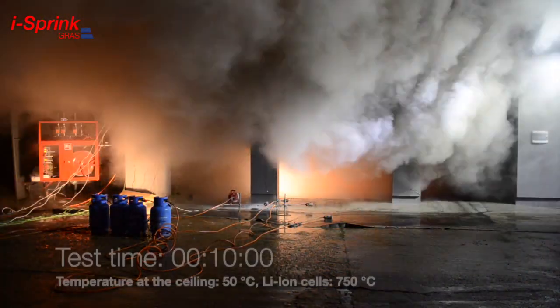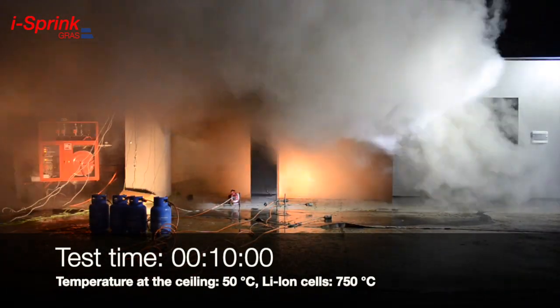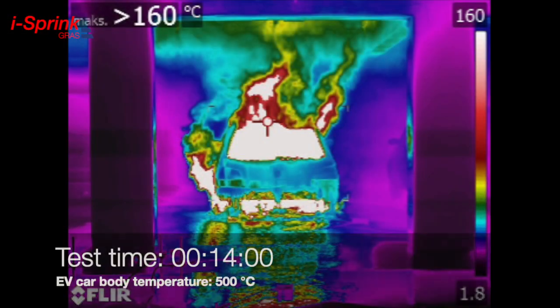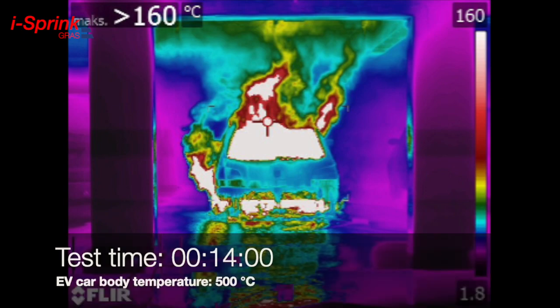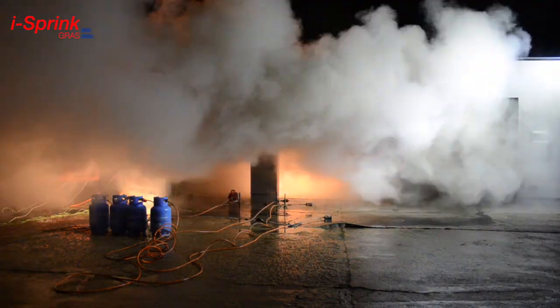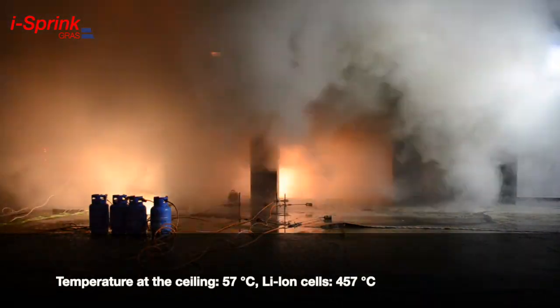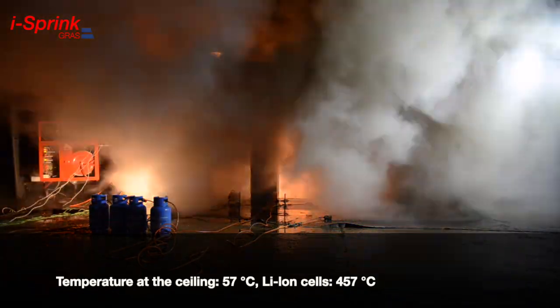At 10 minutes of fire, the temperature at the ceiling above the burning vehicle is only 50 degrees, while on the lithium-ion cells it is 750 degrees. The thermal imaging camera indicates that the temperature of the body of the electric vehicle reaches 500 degrees. Each explosion is accompanied by a rapid increase in temperature and ignition of vehicle components. The i-Sprink sprinkler system effectively reduces the fire temperature: the ceiling reads 57 degrees, while lithium-ion cells read 457 degrees.